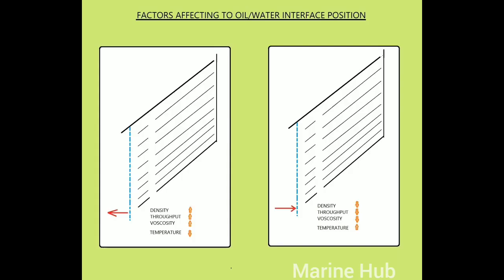In a purifier, if the oil is admitted first, it will simply discharge from the water side. To prevent this, a water seal needs to be applied first.